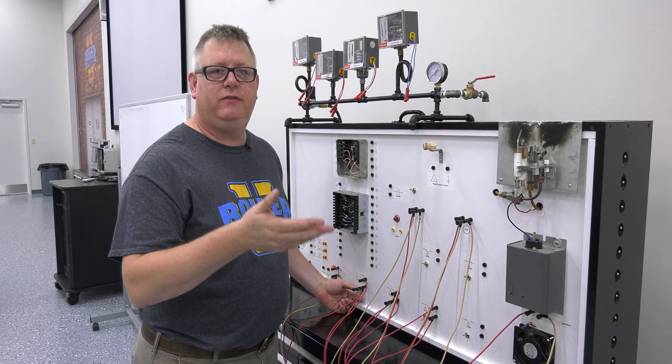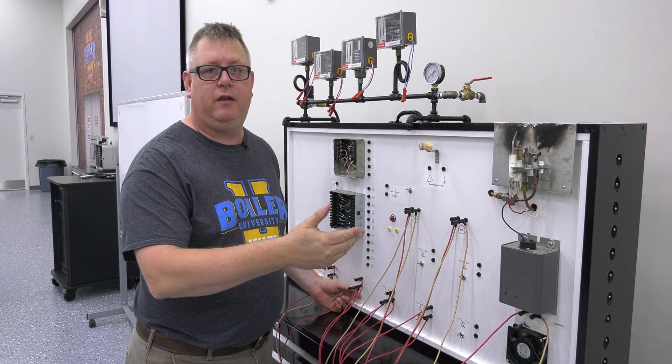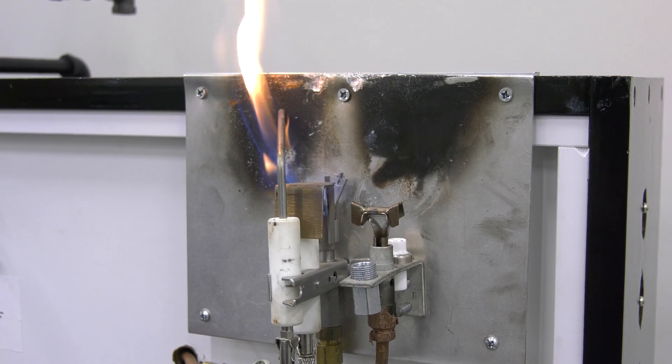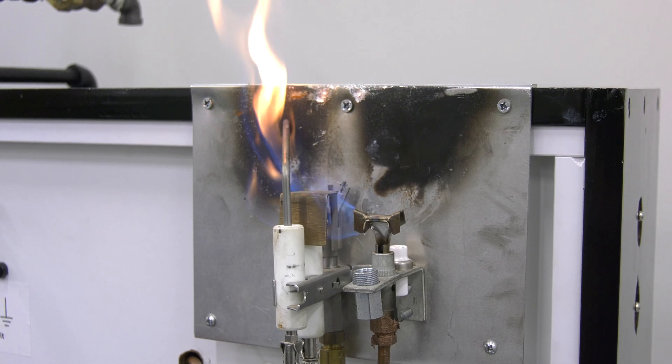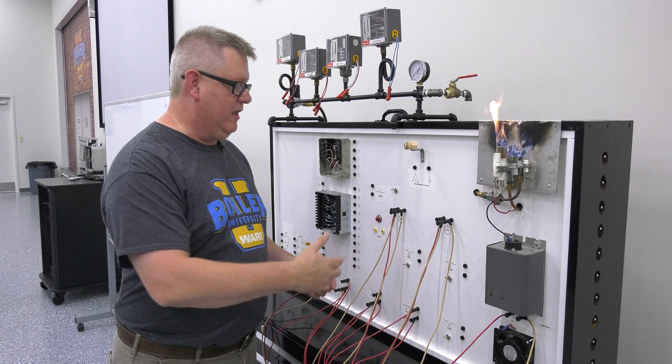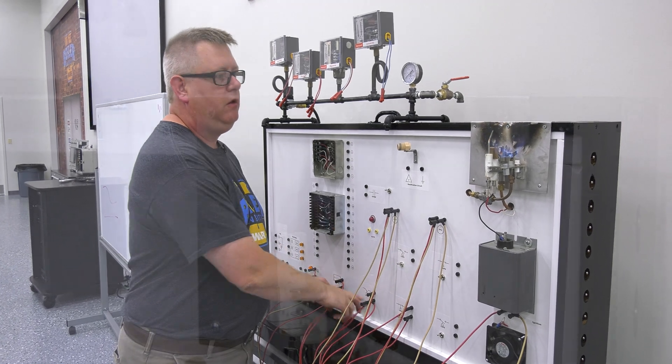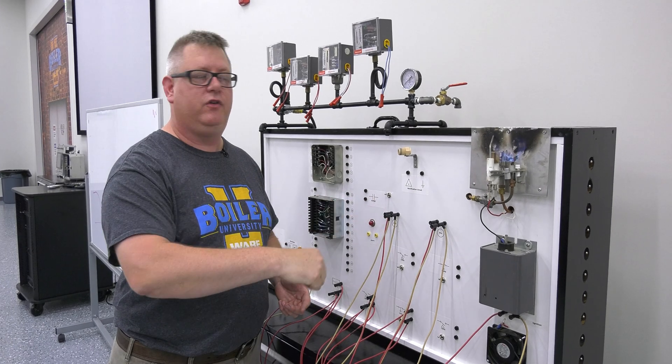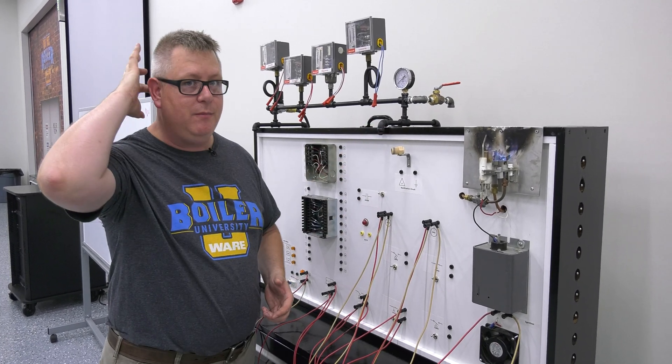The second type of pilot is an interrupted pilot. On our light-off sequence, we'll get spark, we'll get pilot, then we'll get main. Once that's proven, our spark and pilot will extinguish, so we're proving the main flame on its own. That's an interrupted pilot.